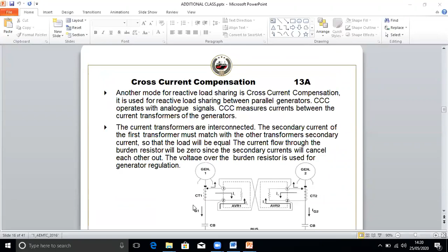Droop CT we have seen, and this is the cross current compensation. Cross current means this: you see, the CT output is connected with the AVR of the other one. Another method of reactive load sharing is cross current compensation. It is used for reactive load sharing between parallel generators. The current transformers are interconnected. The output from here is interconnected to this. The secondary current of the first transformer must match the other transformer's secondary current, so the load will be equal.